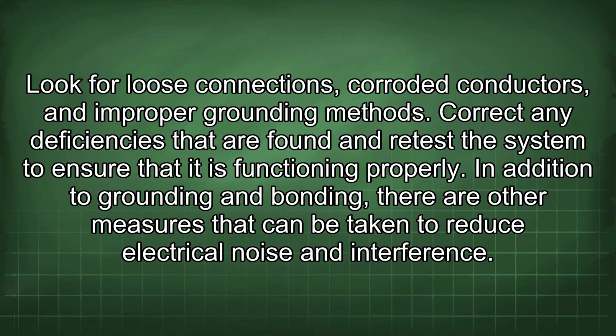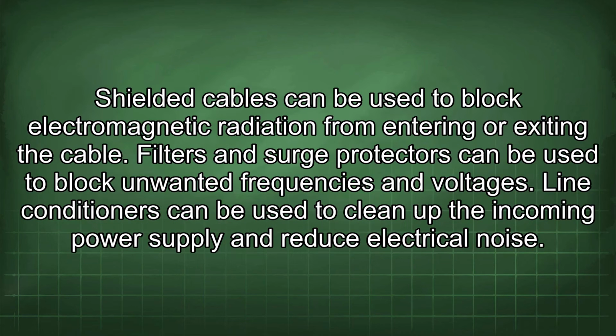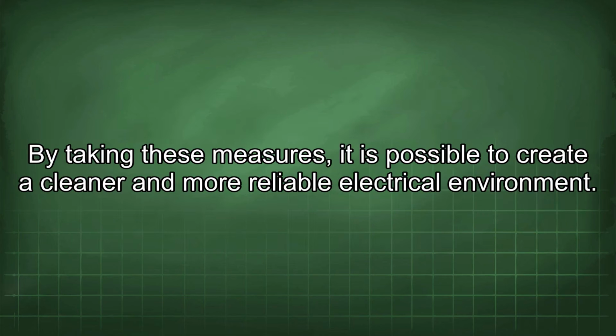In addition to grounding and bonding, there are other measures that can be taken to reduce electrical noise and interference. Shielded cables can be used to block electromagnetic radiation from entering or exiting the cable. Filters and surge protectors can be used to block unwanted frequencies and voltages. Line conditioners can be used to clean up the incoming power supply and reduce electrical noise. By taking these measures, it is possible to create a cleaner and more reliable electrical environment.